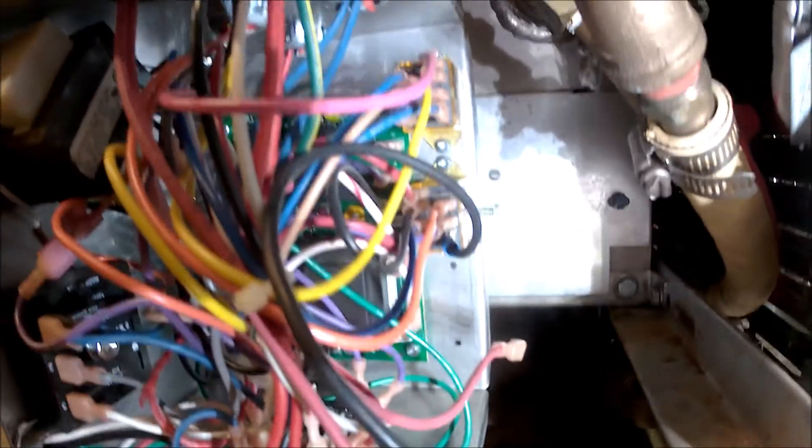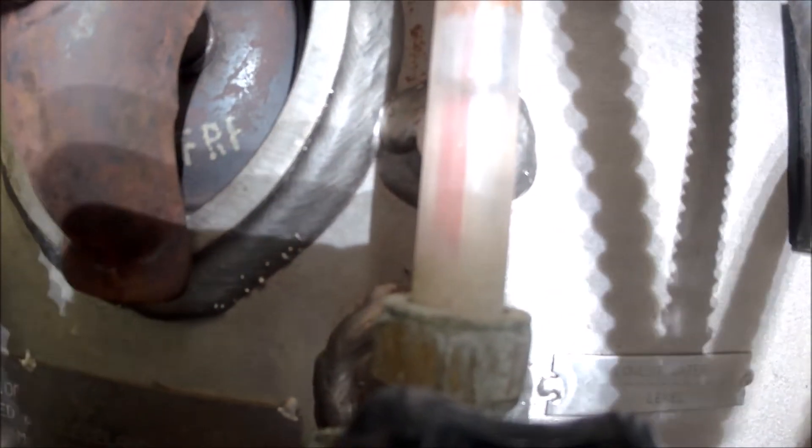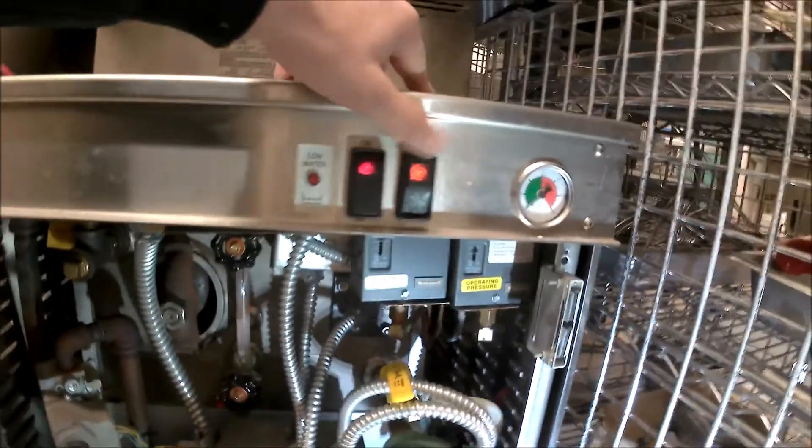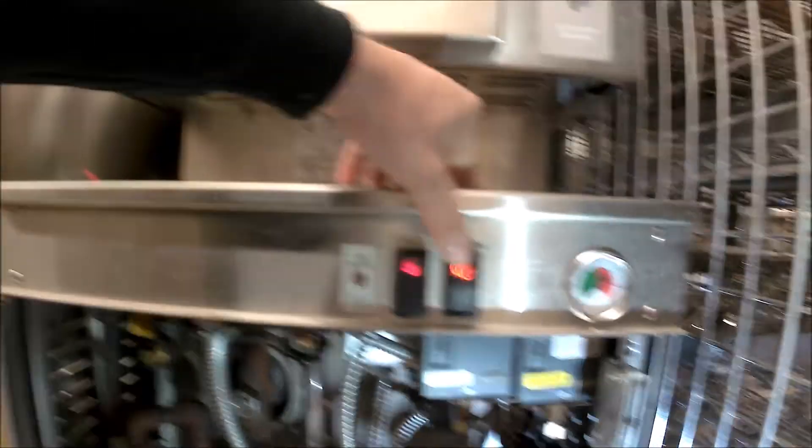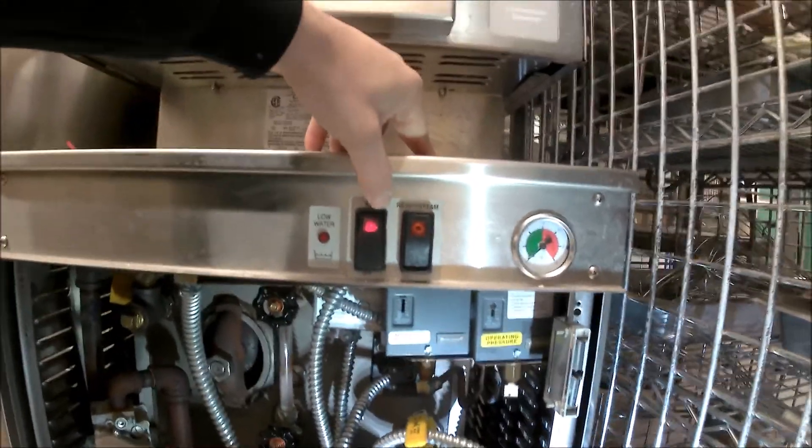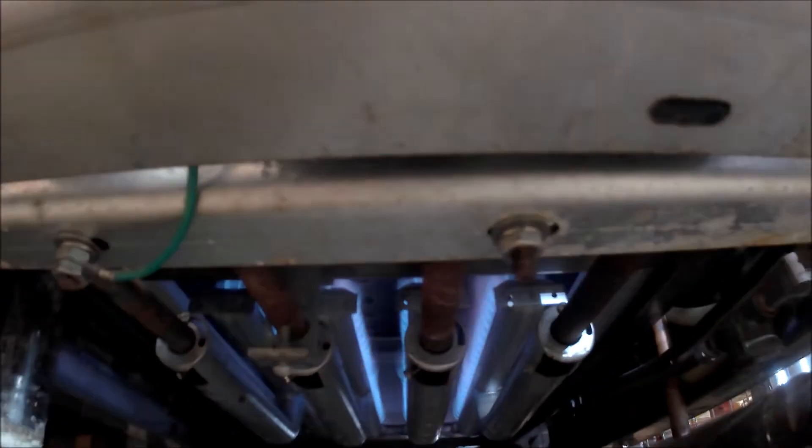First indication - the red light's on, that means the low water probe is satisfied or it's grounding out. The sight glass is moving up nicely. The next hint here is this low water light has come off, that means my high probe is shorted through the water circuit. Let's fire up the boiler and let's see what happens. We have flames! So that confirms the secondary low water cutoff is bad and confirms all my other components are working as they should.